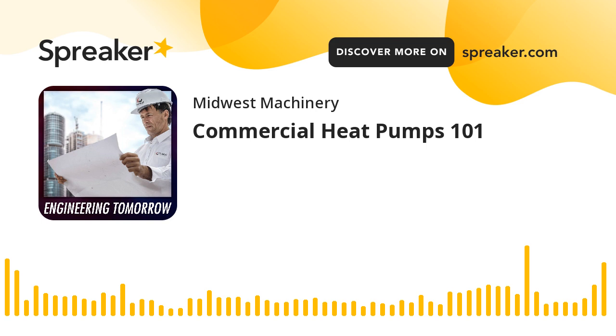Well, it's a good question. First, what I think we're going to primarily talk about today is the water source heat pump, where you're using water to cool the condenser instead of air, which is what you would typically see at your house. You have a condensing unit outside with a fan and a coil that uses air to cool that condenser. What we're going to be talking about is water source heat pumps, where you have a cooling tower or a geothermal well, and you're pumping water through the water source heat pump unit to cool the condenser. So now getting that out of the way, let's talk about what a water source heat pump is.